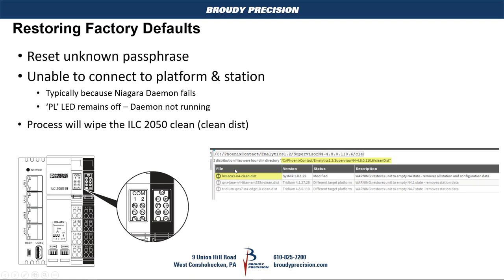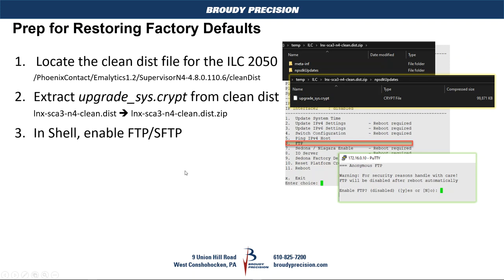The file that gets used is the Linux distribution file for the ILC 2050 — referred to here as SCA3. In preparation for doing the factory restore, you need to locate that clean dist file, copy it to an accessible location, and rename it to a .zip file. Then, from the npsdk updates folder, copy out the upgrade sys .crypt file. Put that in an easily accessible location so that when you go in with FileZilla you can grab it and copy it to the ILC 2050.